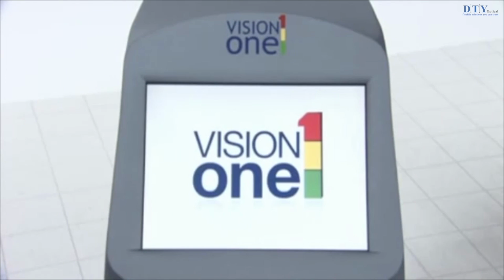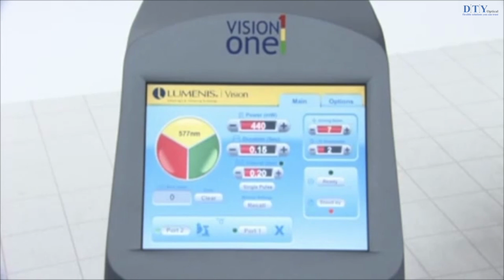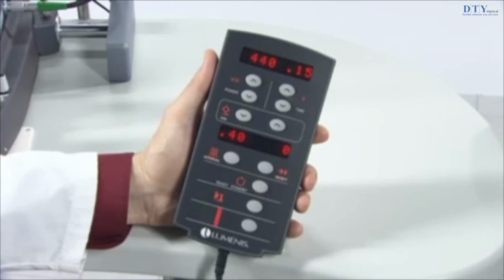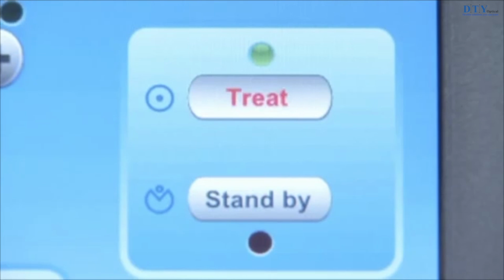When the laser is powered on, the laser emission indicator displays on the control screen to provide visual warning that laser energy is accessible. The indicator continues to display until the laser is powered off. When the remote control is connected to the laser, the Ready Standby selector illuminates to provide an additional visual warning that laser energy is accessible. During treatment, Treat displays on the control screen and illuminates on the remote control.